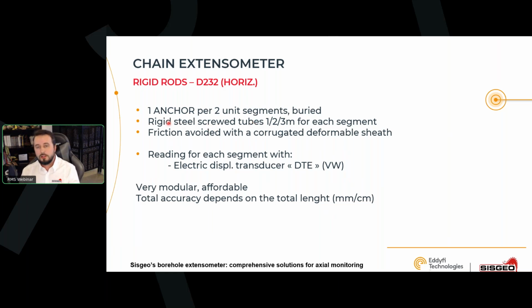Here, the rod is a chain of tubes screwed together, rigid stainless steel tubes of 1, 2, or 3 meter length, which you can assemble over several decameters since you can extend the distance between two anchors as you want. Friction is avoided by a deformable sheath, and each segment has its own electric displacement transducer for reading.